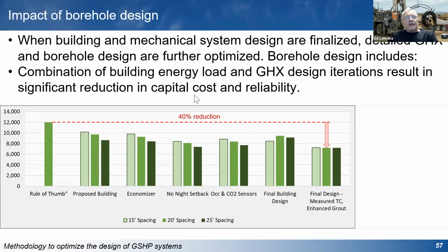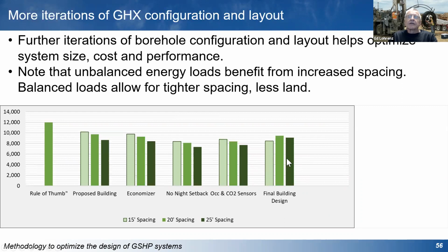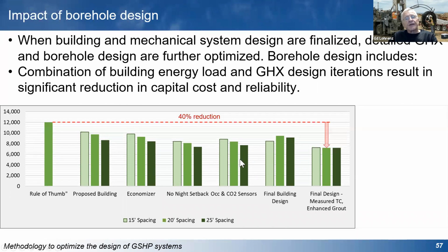So the other thing that can be done is really look at the borehole design. The original ones up to here were looked at, the only parameter that was changed was the spacing between the boreholes, and we modeled it with standard grout initially, so about a 0.4 grout, and really nothing special on it. Once we started looking at the borehole configuration, the borehole layout, and the borehole design, we were able to reduce the size of the boreholes even further. We're down to about 7,300 feet of drilling.